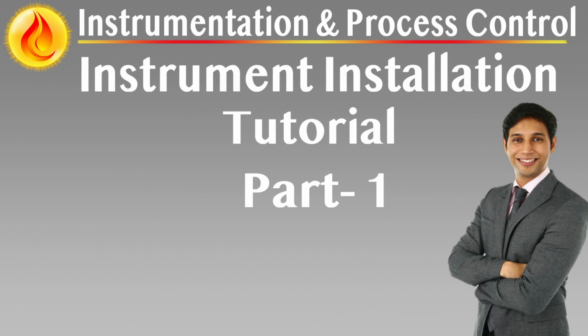Precision access and isolation control. Online instrumentation must incorporate robust, dedicated primary isolation valves to enable safe removal, calibration, or maintenance without interrupting the process. These valves act as the first barrier of protection and must be rated for full process pressure and fluid characteristics. Where instrumentation is deployed in parallel to extend range coverage, shared isolation may be employed only when each instrument has its own independent secondary isolation. This ensures operational safety and containment even during partial loop servicing.